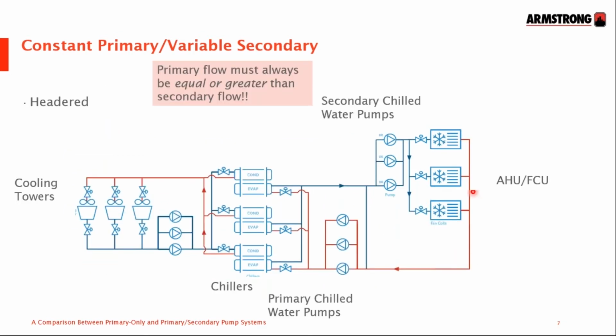Oh, the other thing to mention, of course, is that the primary flow must always be more than the secondary flow. The water in the header here must always be going in this direction, down, rather than that way up here. If the flow rate in the secondary circuit is more than the flow rate in the primary circuit, the warm water will come back in here and go back into the building, causing the system to spiral out of control with excessive numbers of chillers and cooling towers working for the actual load itself. So that's one point to know. Primary flow must always be equal to or greater than the secondary flow.